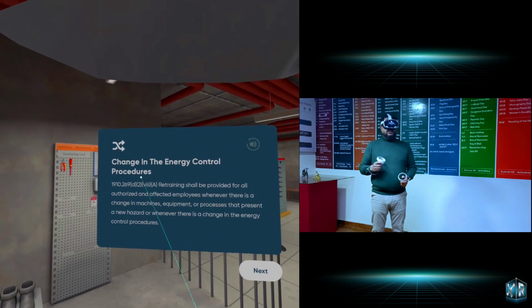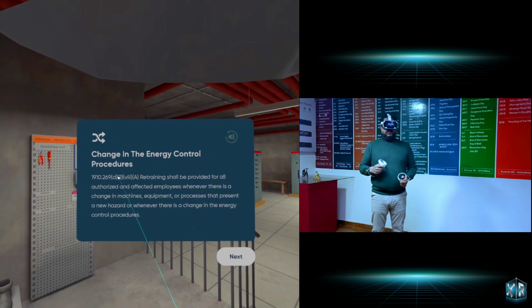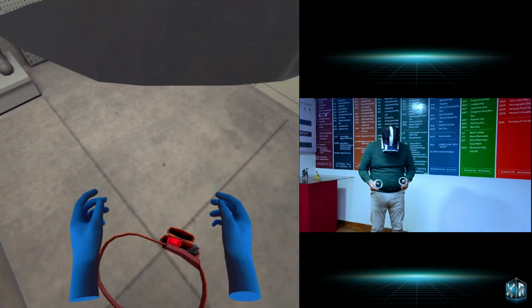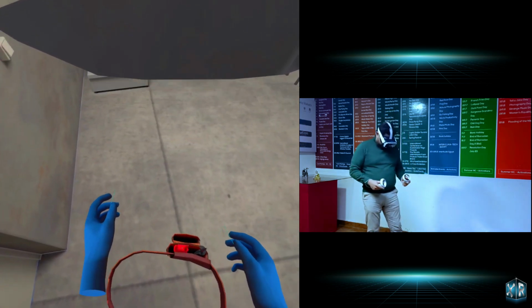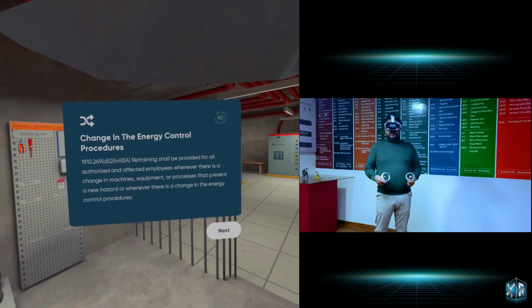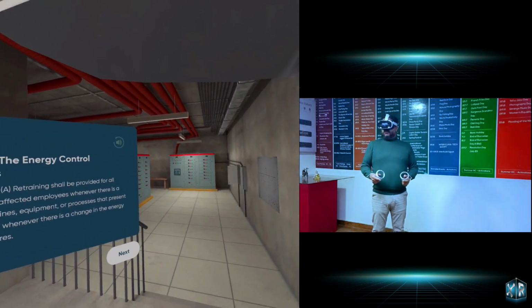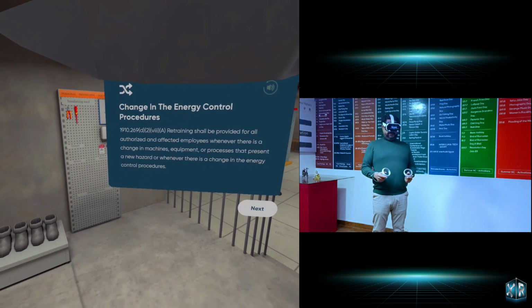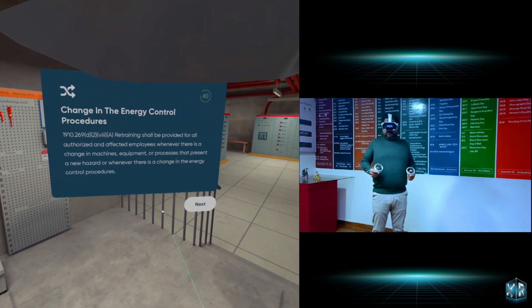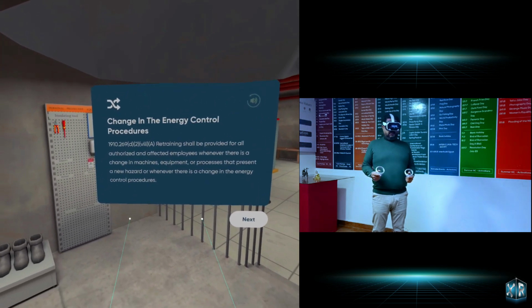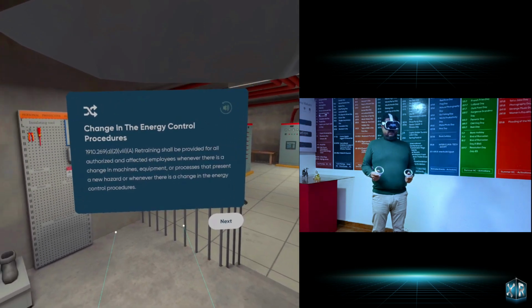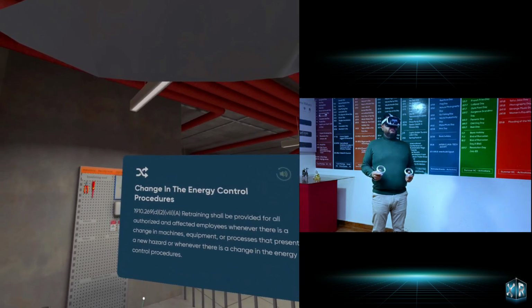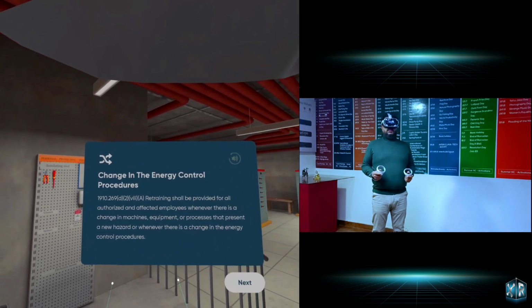Change in the energy control procedures. At some point, the tagged-out circuit breaker had been cross-wired with the other breaker, and thus the panel was not de-energized. According to the OSHA standards, retraining shall be provided for all authorized and affected employees whenever there is a change in their job assignments, machines, equipment, or processes that present a new hazard, or any time there is a change in the energy control procedures.